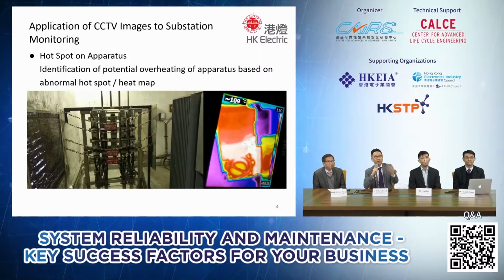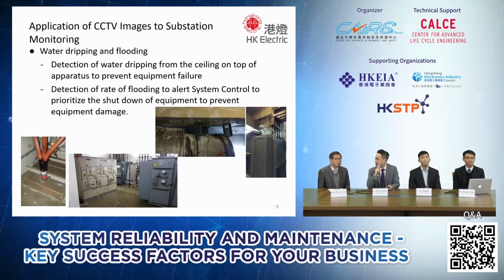But developing a hotspot is not a 1 or 2 second event, it may take half a year. That means if we can deploy something monitoring the hotspot full-time, we can see the trend as it develops. So we are deploying IR cameras to monitor the panel and detect any potential hotspot developing, so we can act before it becomes a permanent fault, further improving our supply reliability. This is one of the use cases we are doing now.